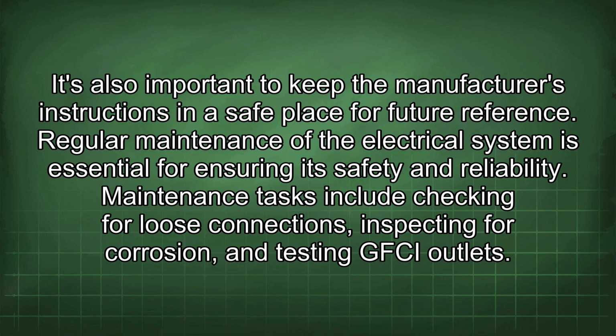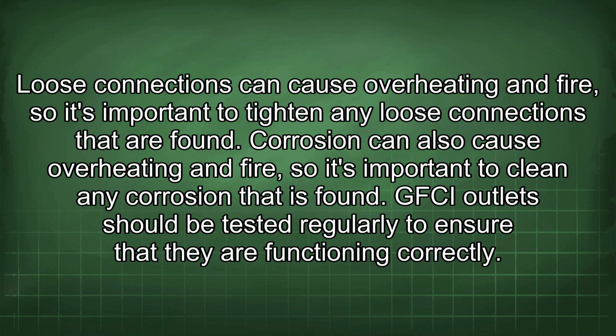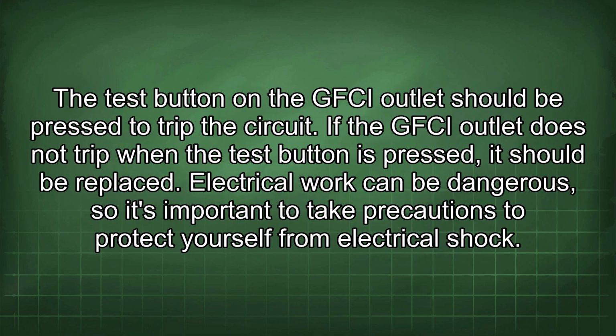Regular maintenance of the electrical system is essential for ensuring its safety and reliability. Maintenance tasks include checking for loose connections, inspecting for corrosion, and testing GFCI outlets. Loose connections can cause overheating and fire, so it's important to tighten any loose connections that are found. Corrosion can also cause overheating and fire, so it's important to clean any corrosion that is found. GFCI outlets should be tested regularly to ensure that they are functioning correctly. The test button on the GFCI outlet should be pressed to trip the circuit. If the GFCI outlet does not trip when the test button is pressed, it should be replaced.